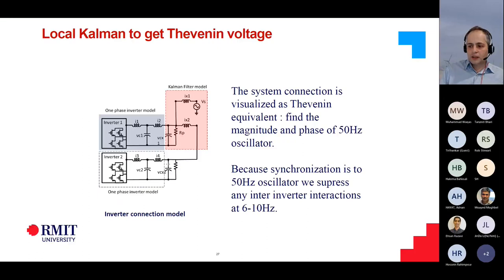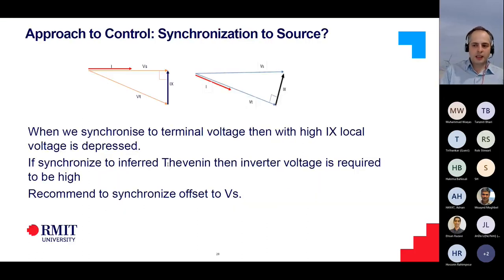However, there's a problem because of the phasor difference between the terminal voltage of the inverter and the voltage we see from a point further away from the terminal. We need to find a compromise to ensure the inverters do not become unstable. That's what the Kalman filter does: it creates and estimates the reference point, compensates it, and feeds it to the inverter to ensure the inverters follow that good reference point and aren't distorted by the weak signal or weak reference of the terminal voltage.